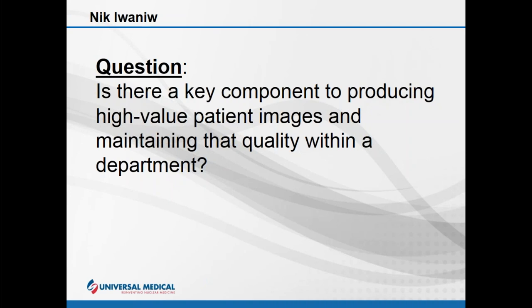Related to the camera, and separate from the motions but vitally important, are the detector operations. That's what actually produces the image. Is the uniformity, the calibration, the resolution of that up to performance standard for optimal imaging? These all need to meet quality standards in order to create quality imaging.